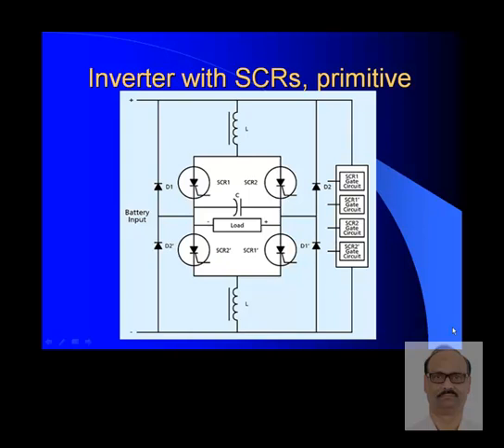Inverter with silicon-controlled rectifiers (SCRs) is primitive technology, used perhaps in the 1960s and 1970s. A serious drawback is commutation: once an SCR conducts under DC conditions, it continues to conduct. Commutation must be managed by a capacitor, and careful selection of this capacitor is critical for inverter applications.